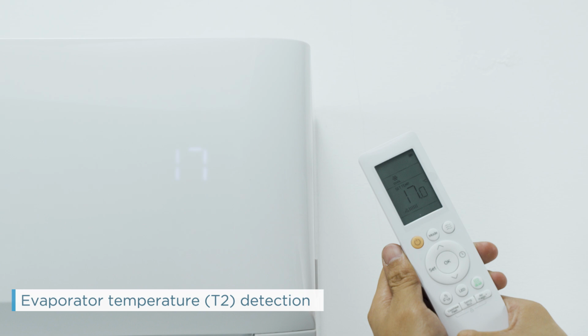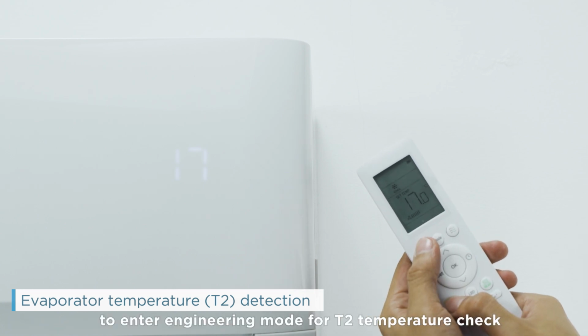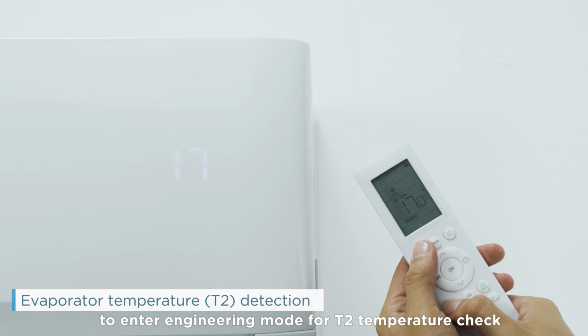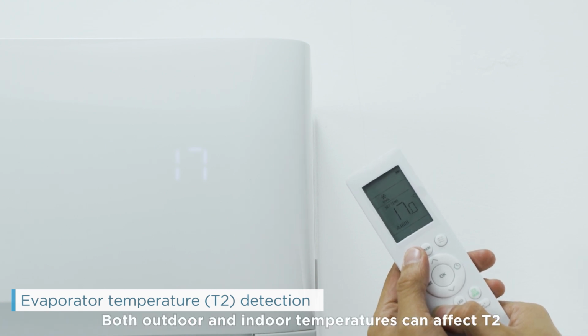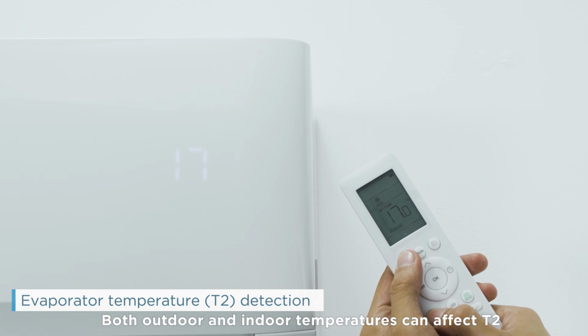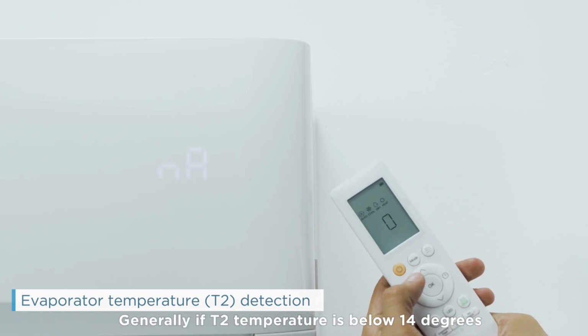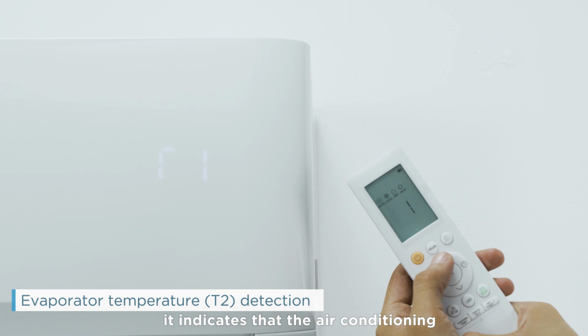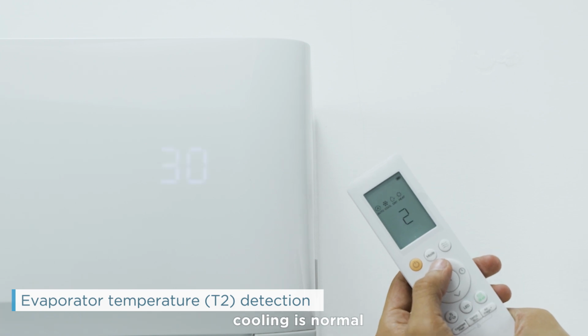Evaporator temperature T2 detection. Use the remote control RG10 to enter engineering mode for T2 temperature check. Both outdoor and indoor temperatures can affect T2. Generally, if the T2 temperature is below 14 degrees, it indicates that the air conditioning cooling is normal.